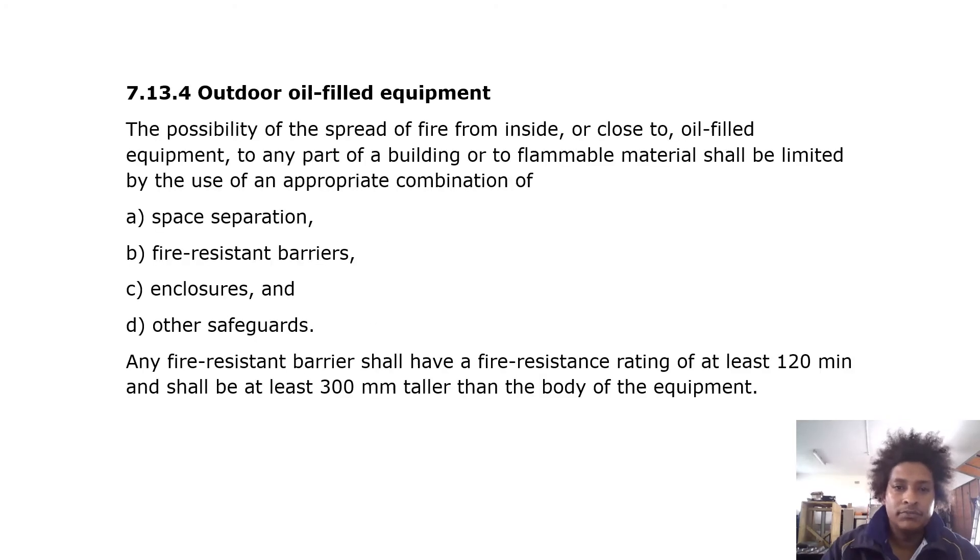For outdoor oil-filled equipment, the possibility of the spread of fire from inside or close to oil-filled equipment to any part of a building or to flammable material shall be limited by an appropriate combination of space separation, fire-resistant barriers, enclosures, and other safeguards. Any fire-resistant barrier shall have a fire resistance rating of at least 120 minutes and shall be at least 300 mm taller than the body of the equipment.